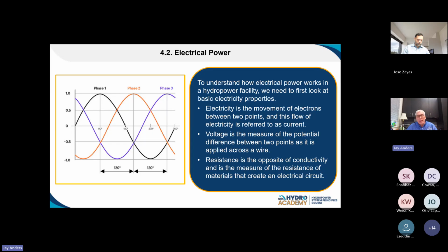Once we get it up and generating, we can start paralleling outside of the plant. And when I say paralleling, what I mean is connecting our generating station to the grid. We parallel, and the reason we use that word is we have three phases, A, B, and C phase. Everything has to be in phase. The voltage that we're generating, we have to get it exactly in phase with the system we're connecting to.